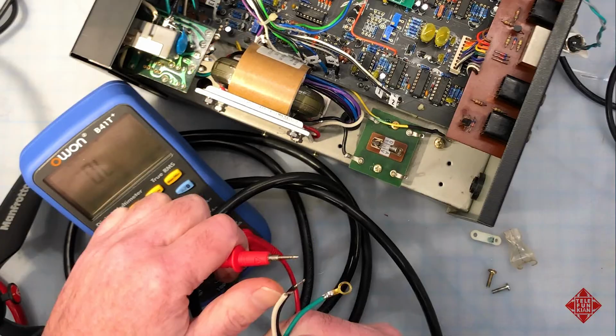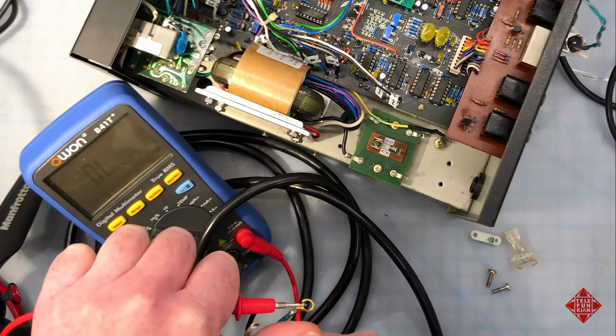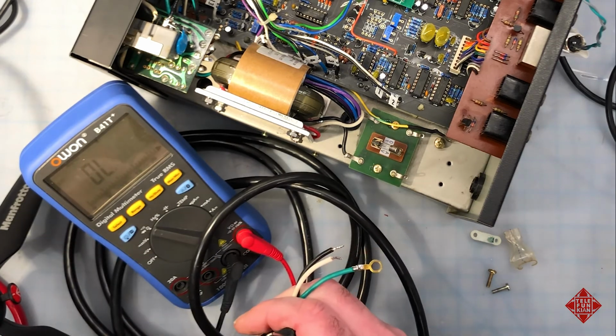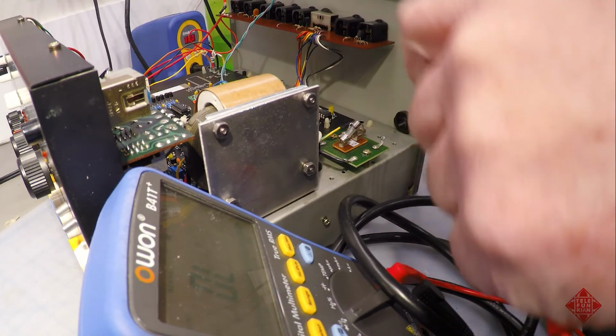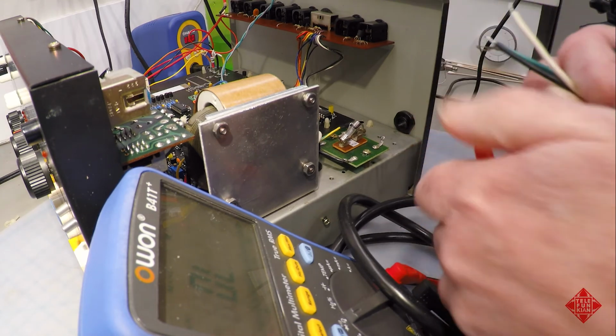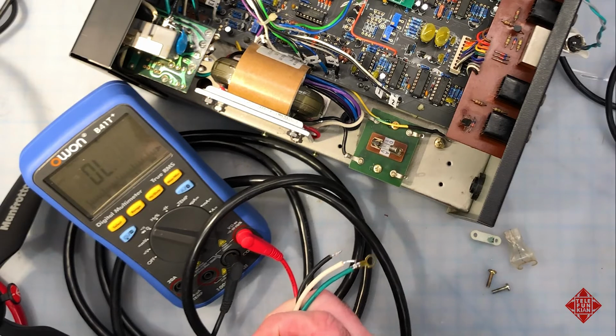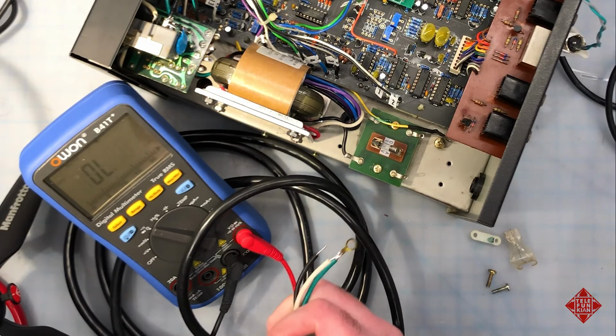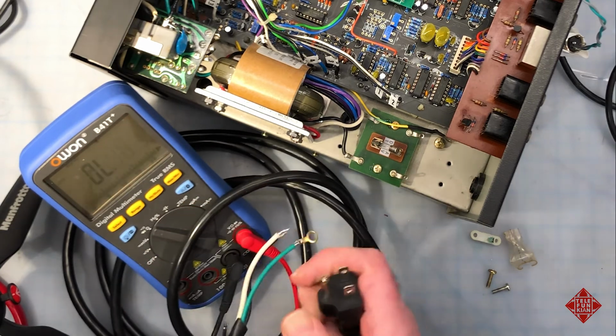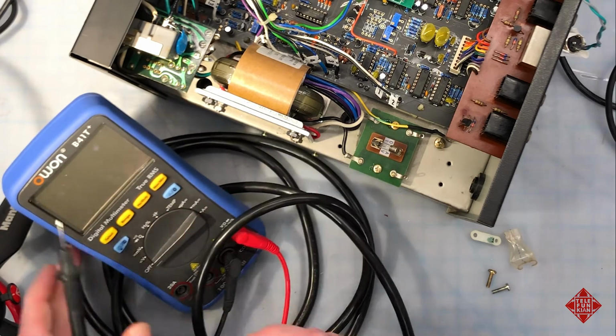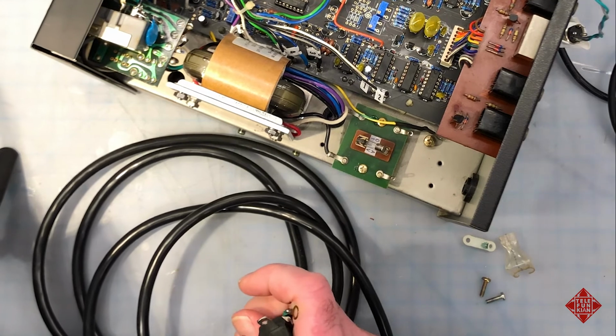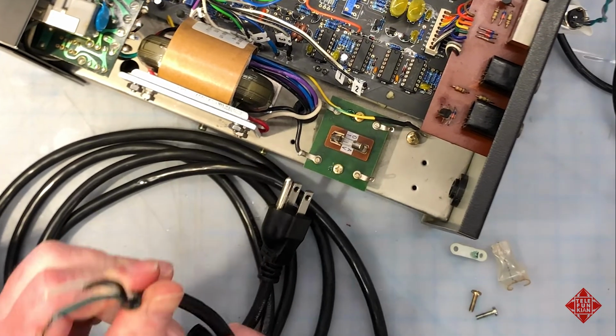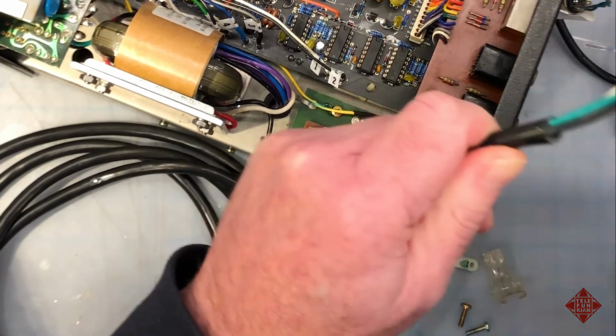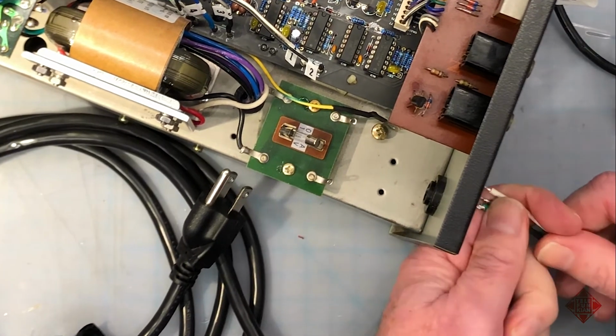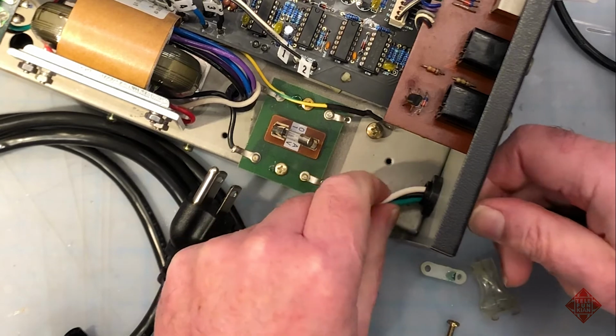And so this is the live, and it should be connected to the black wire, and we'll test that, and indeed it is. It's not connected to the white, nor is it connected to the ground. And similarly, the neutral wire is connected to the white, is not connected to the black, is not connected to the ground. And just for thoroughness, we'll make sure the ground is indeed connected to the ground pin, and indeed we have connectivity there.